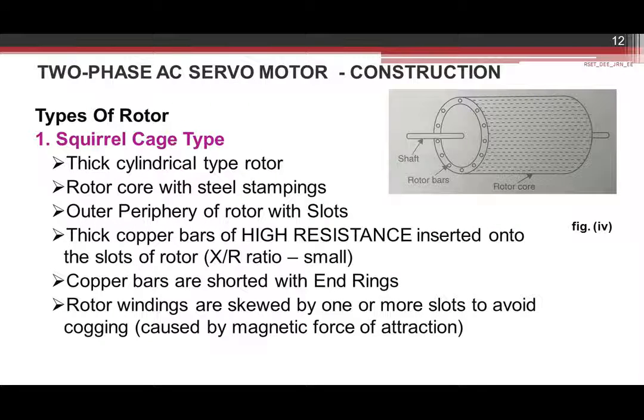There are three rotor configurations. The first type is the standard squirrel cage rotor — thick cylindrical in shape, with a thick rotor core made up of steel stampings and thin laminations. The outer periphery is slotted to accommodate thick copper bars of high resistance, maintaining a small X/R ratio. Copper bars are short-circuited with end rings, and rotor windings are skewed by one or more slots to avoid cogging caused by magnetic force of attraction.